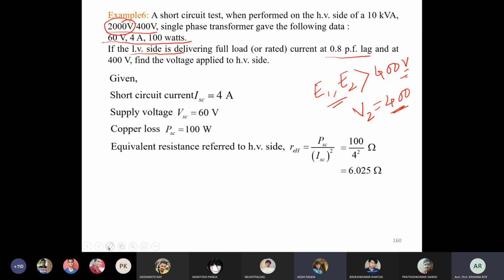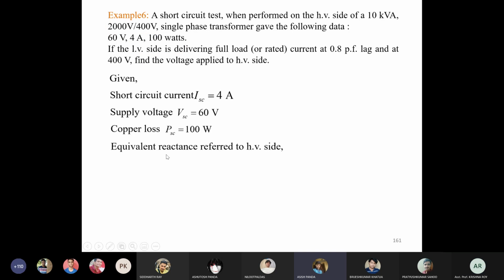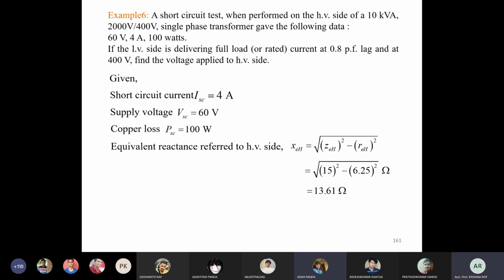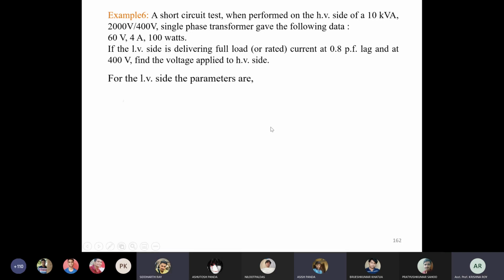Next, calculate ZEH, that is VSC by ISC, which is 15. Calculate XEH, root over ZEH square minus REH square, which is 13.63, or 13.61 ohm. So once we get REH and XEH, we can find the parameters referred to the low voltage side.